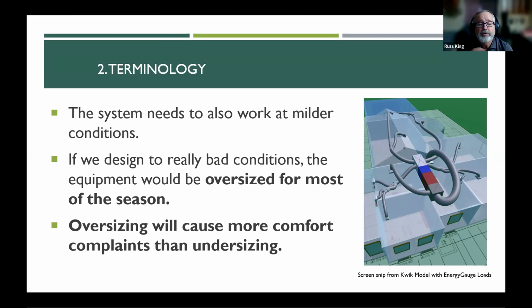The only way that would not be true is if something happened to the house, like they added a bunch of glass or they removed all the ceiling insulation or the house developed a huge leak or something crazy like that. But that's the opposite direction we want to go, right? We want the houses to be more efficient so the equipment can get smaller and smaller, all right? So hopefully I just can't emphasize enough that oversizing equipment to be safe is not a good idea.